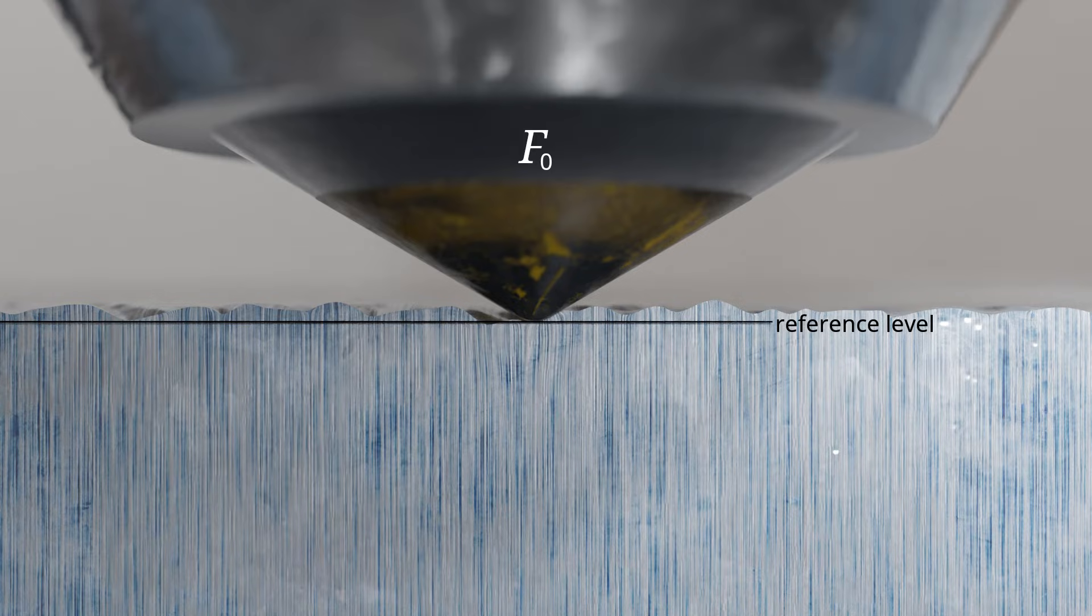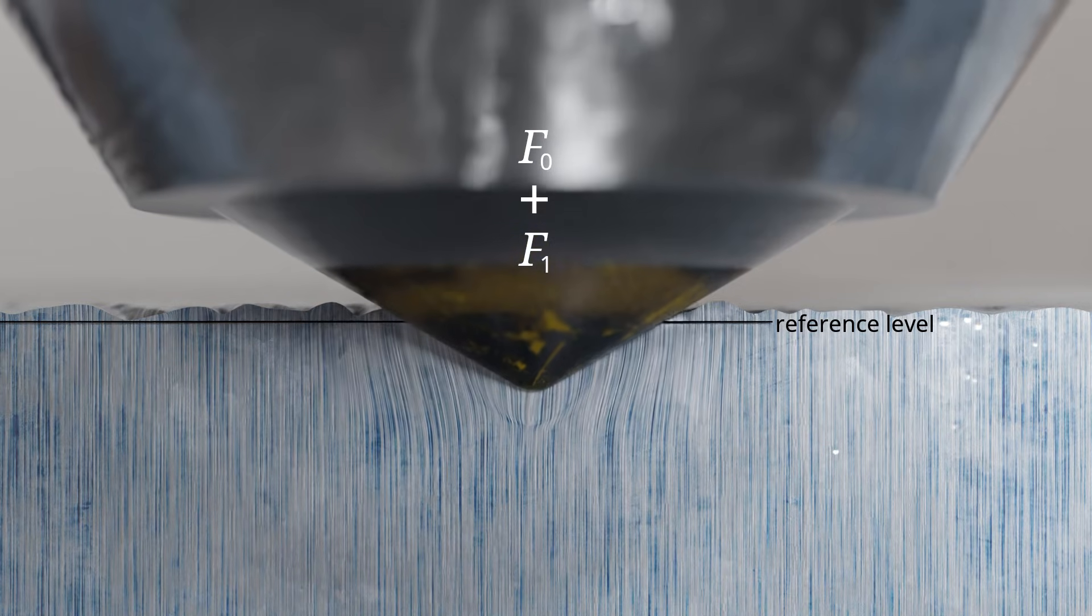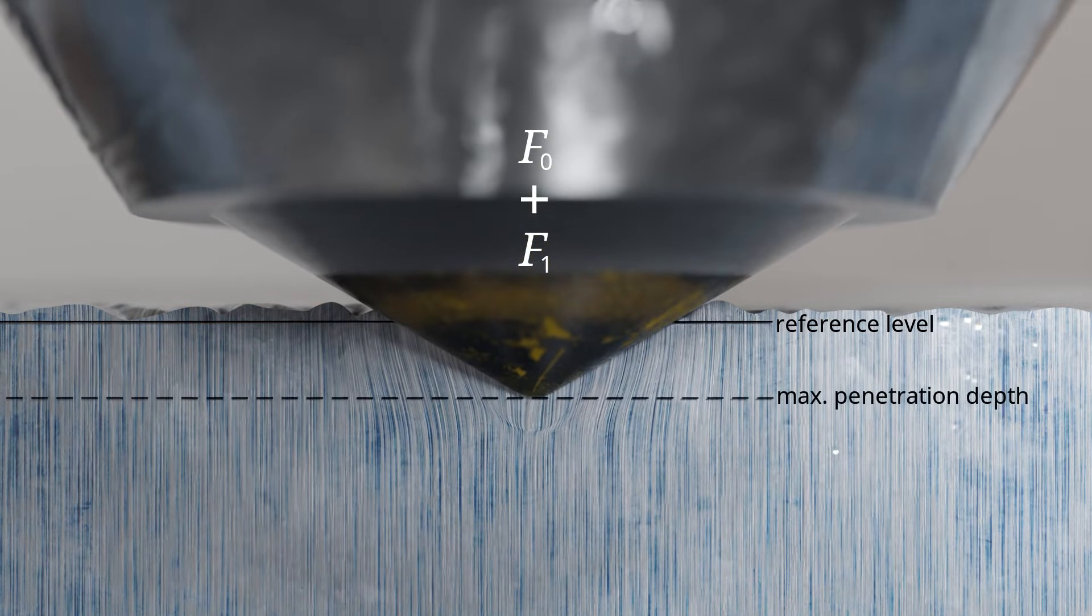Next, in addition to the preload, the actual test load F1 is applied. The indenter penetrates the material surface with a total force F, which is the sum of F0 and F1. The appropriate test force F1 is determined from reference tables based on the type of indenter used and the material being tested.